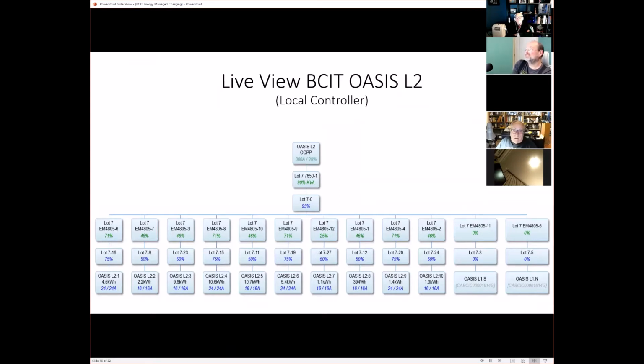So that was the engineering view. Now, on runtime, this came off of our local controller that was actually doing the function. At the time when I took this snapshot, you can see all the cars are busy charging. They're not all taking 32, and they're limited to something less than 32 amps. There's nothing on the two 120 volt outlets. But when we look up at lot 7-0, it says it's 95% full. So we've done a pretty good job of maximizing the power that's available in that panel. And our kVA limit was at 90%.